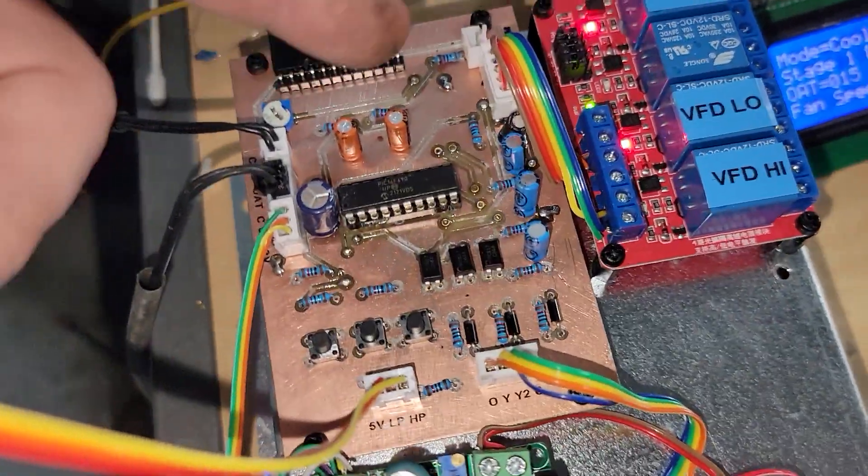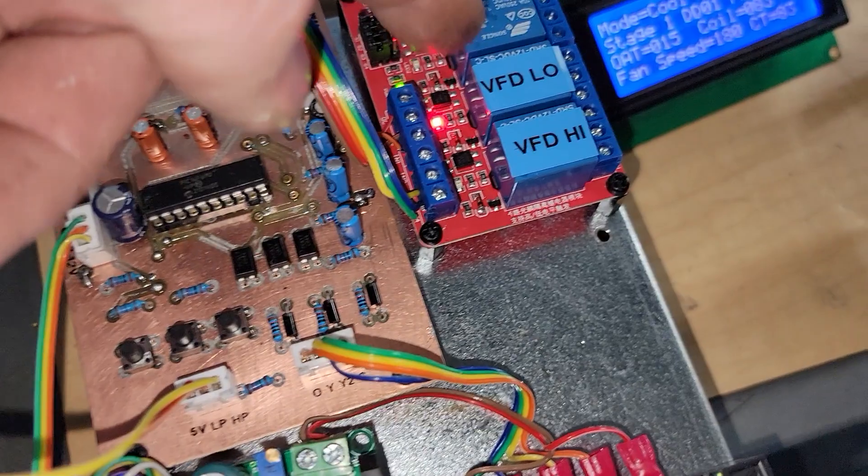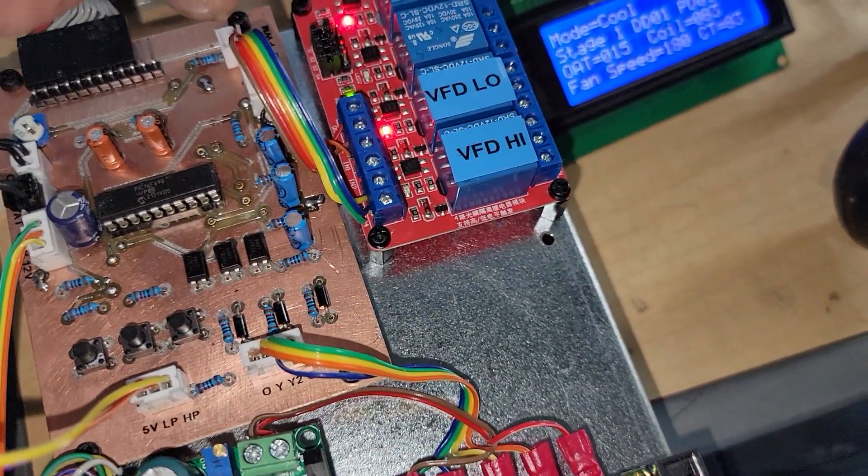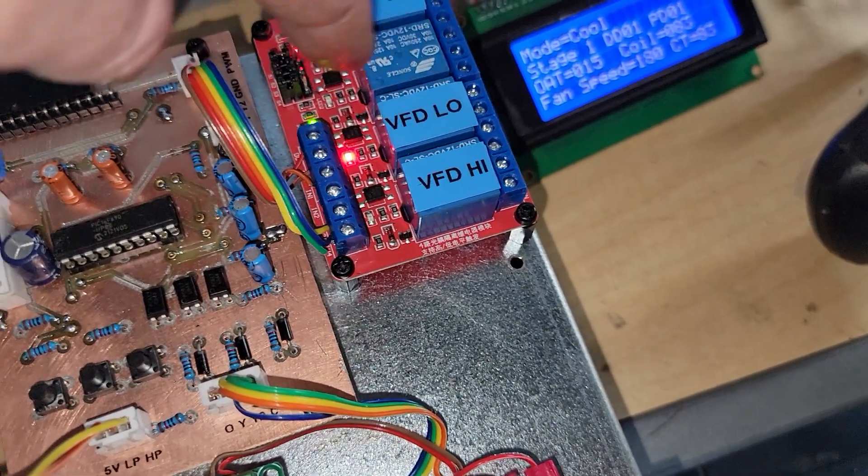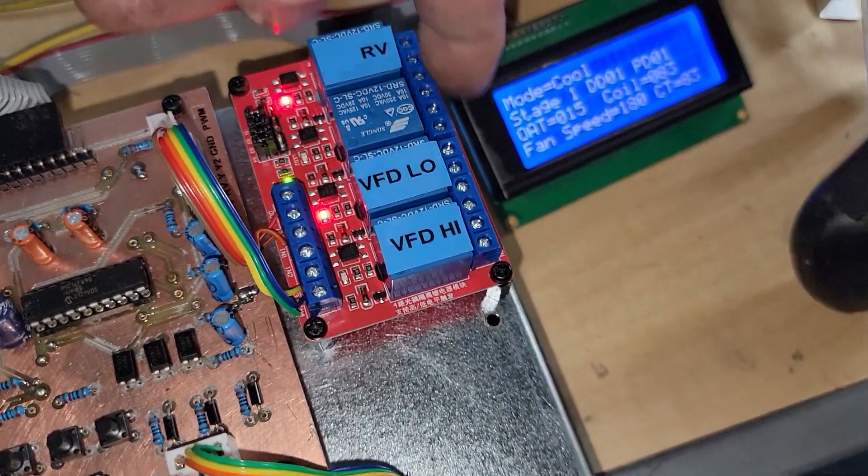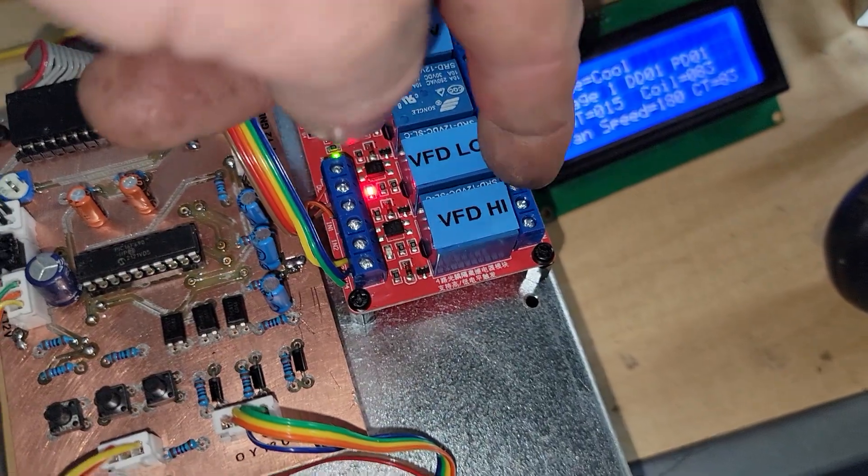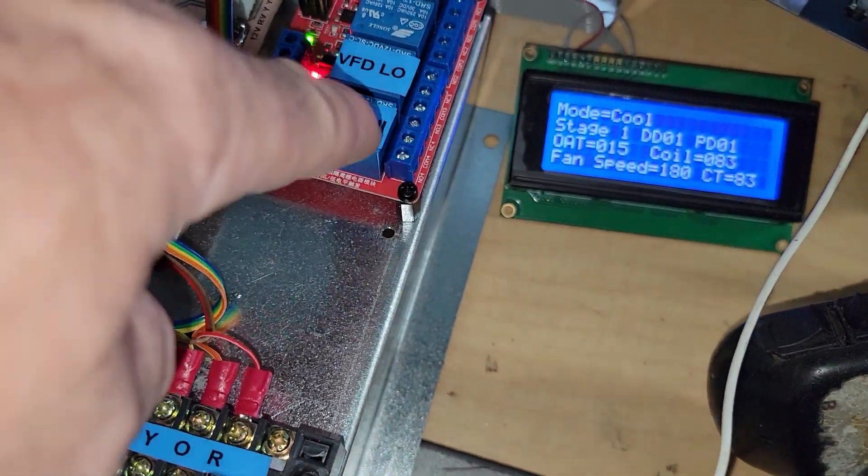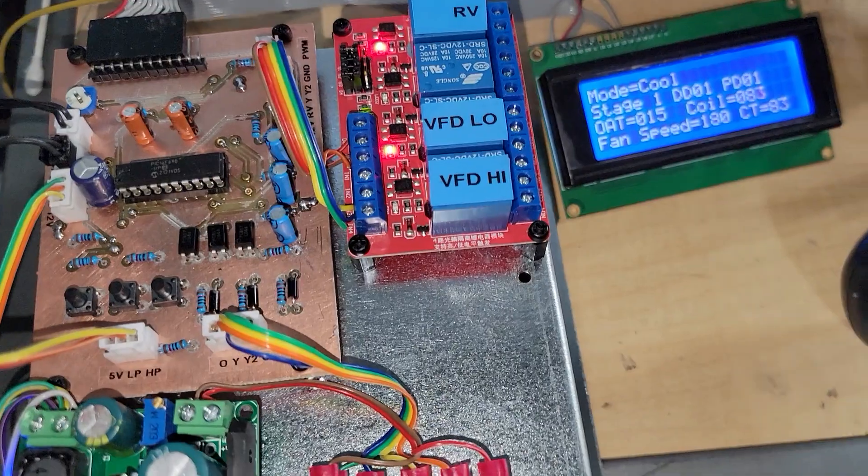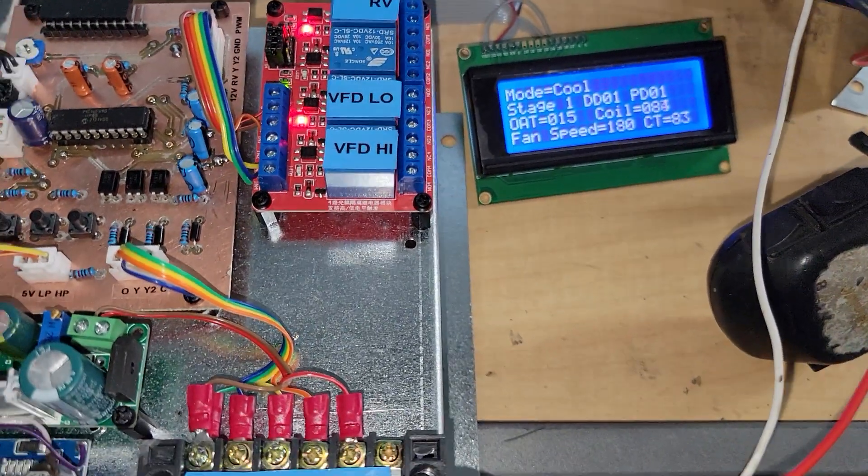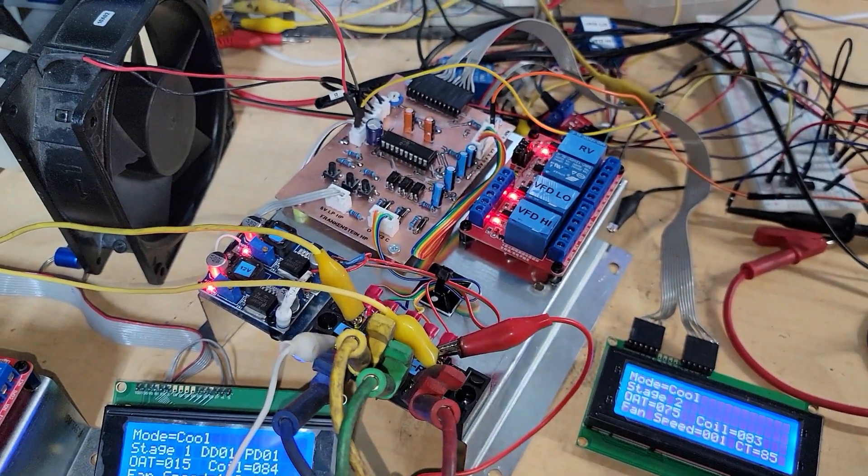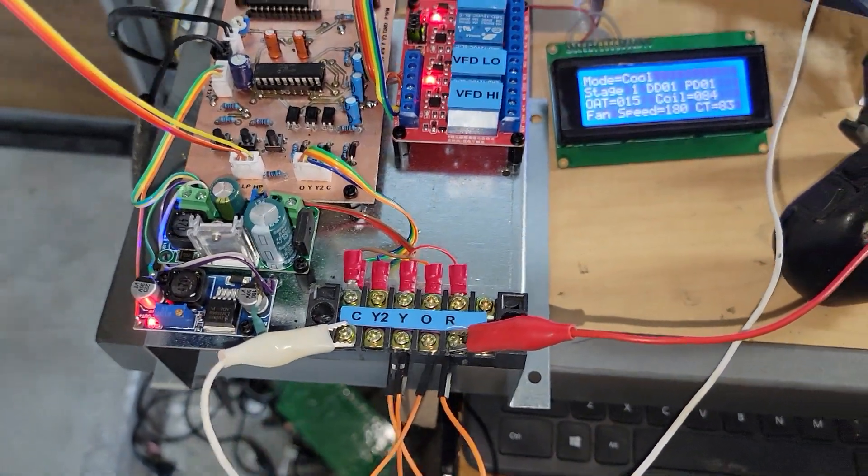The processor has the outputs going over here to the relay board. I'm using reversing valve which is high voltage connections there, so I put a separation here - didn't use this one. High voltage on this strip, low voltage DC 24 volts from the VFD interacting here. I could click this second stage on, kick that on.